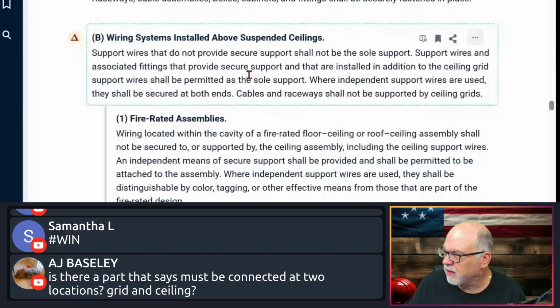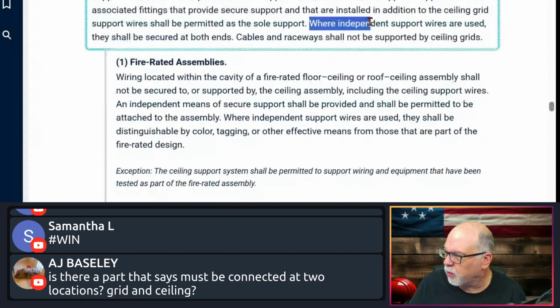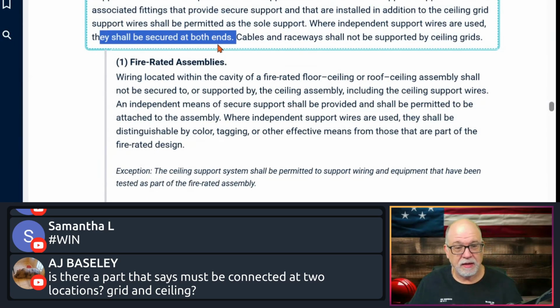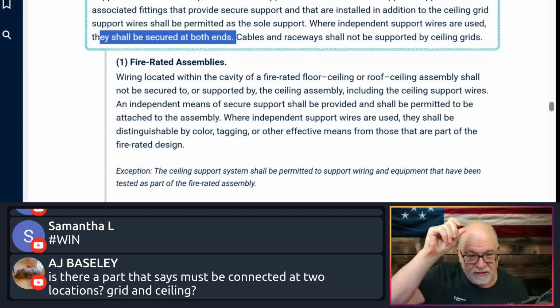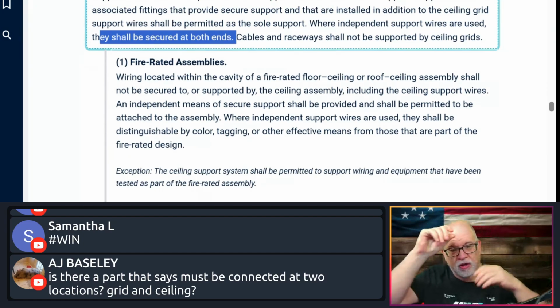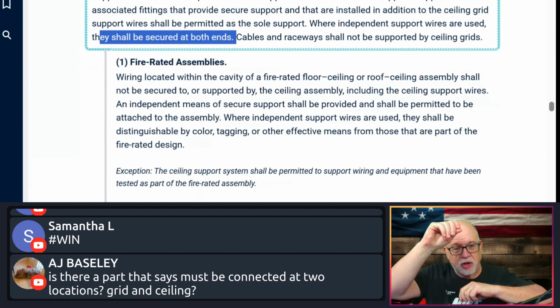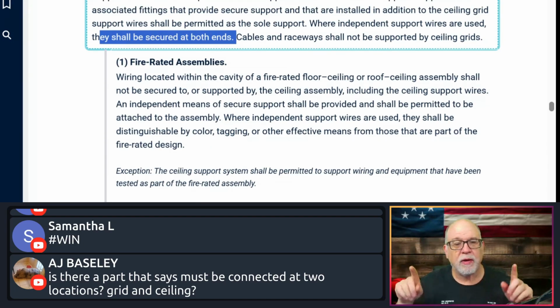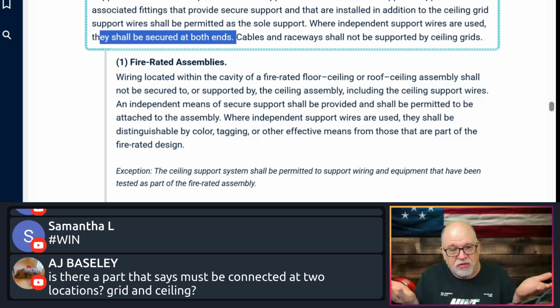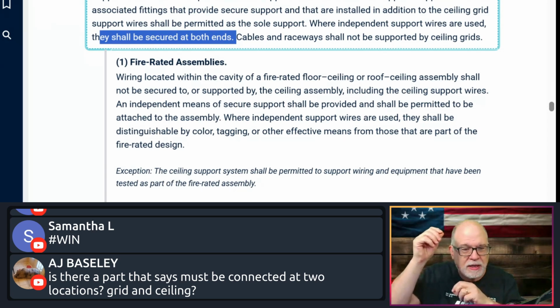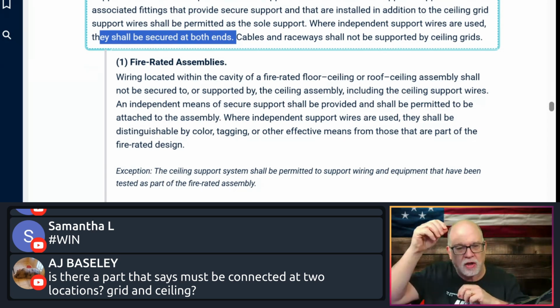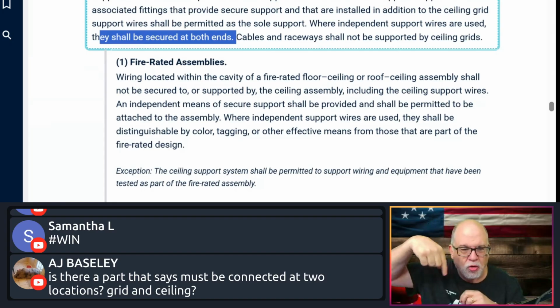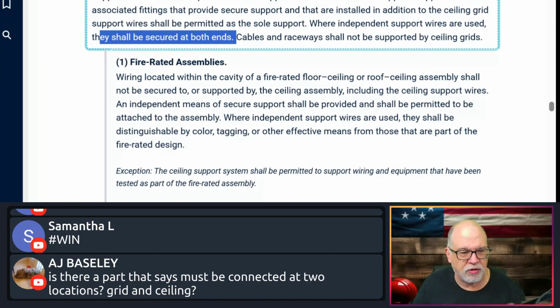Right here, this is where independent supports are being used. That's what you're running, independent supports. They shall be secured at both ends. One at the ceiling or whatever the supporting structure is, and the other end could be to the grid. It's just in addition to any other wires that may be run to support the ceiling grid structure. These are your own independent wires, but they have to be taut. They have to be connected at both ends. No trapeze, no swinging.